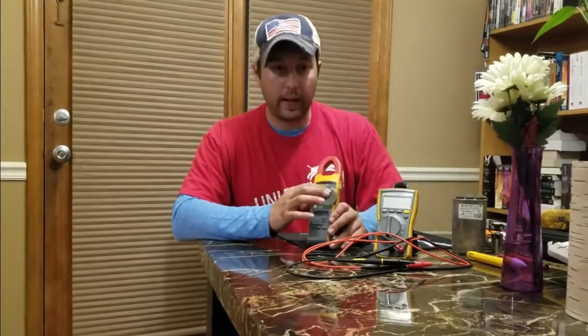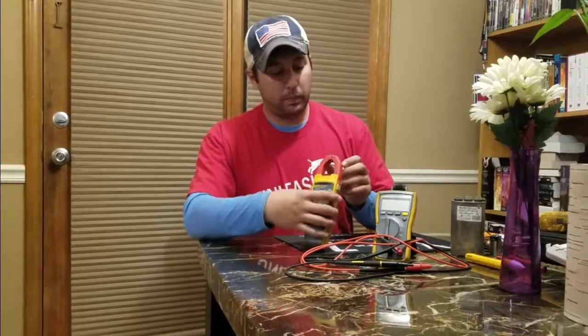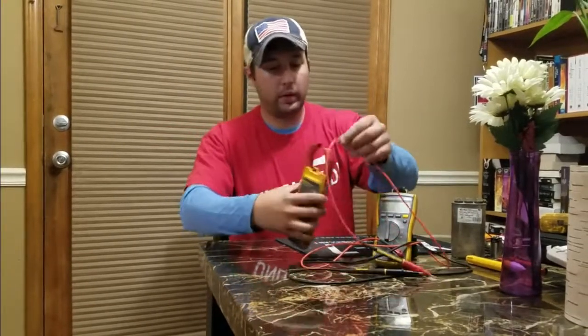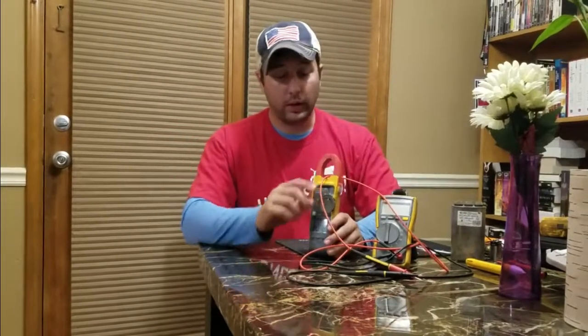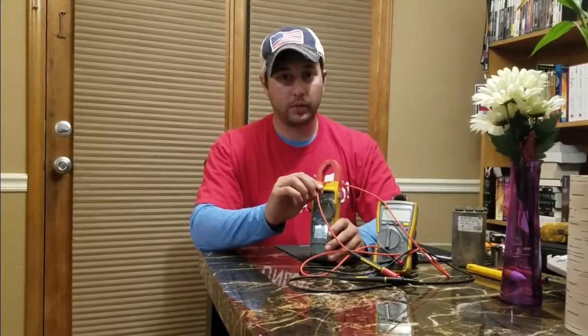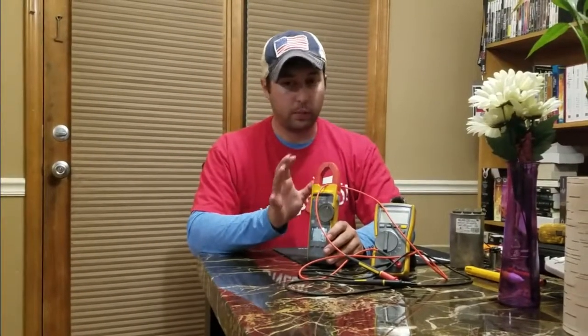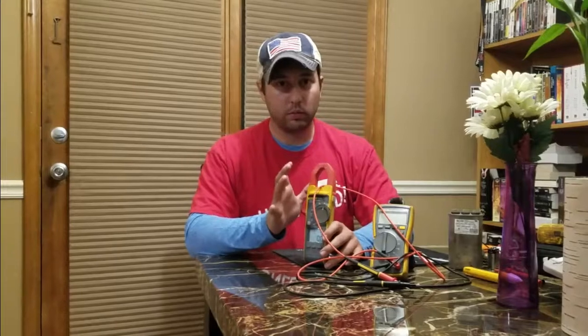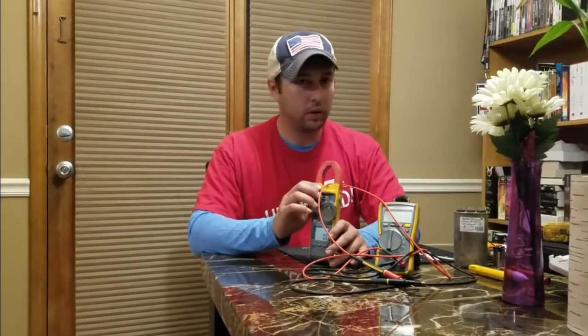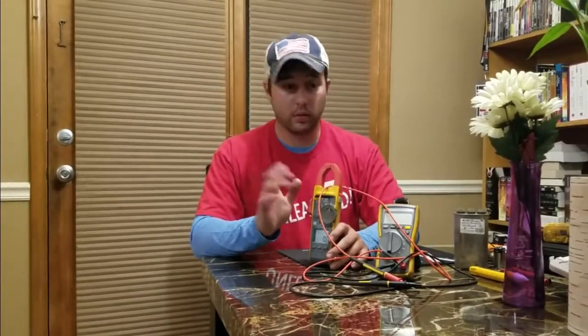So if we go to amps, we can open this up and clamp it around the wire like that. You only do one wire at a time when you're checking amps. If you check more than one wire at a time, it's going to tell you 0 every time, I promise you. Just take my word for it, or go out and try it.